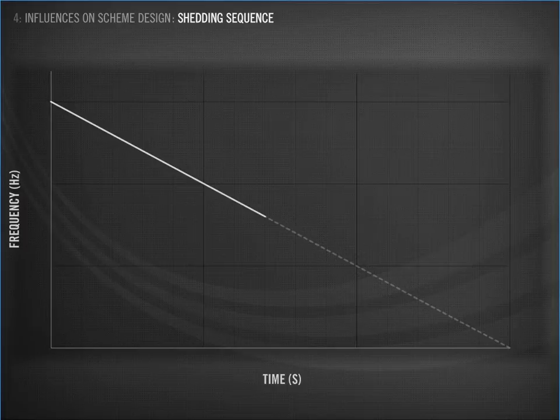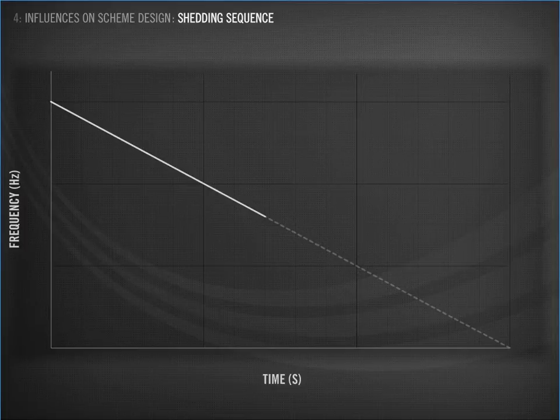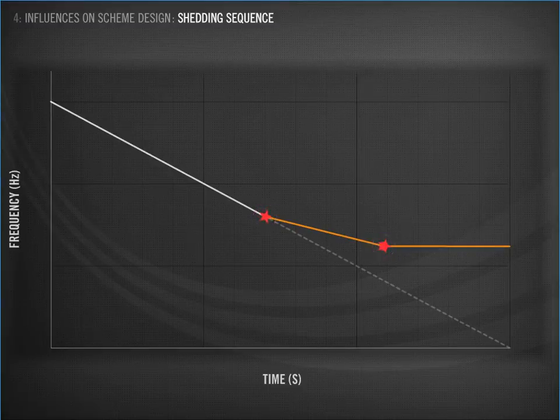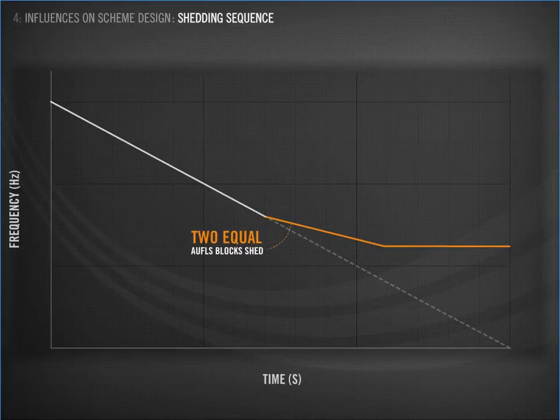In this hypothetical example, we know the total amount of load we need to shed to restore balance to the power system. We divide this into two equal-sized blocks. Block 1 hits the brakes, slowing the frequency decline. It's still falling, so the second block trips. Because exactly the right amount of load was shed, the frequency decline is arrested and the line levels out. We call this the two equal blocks scheme.